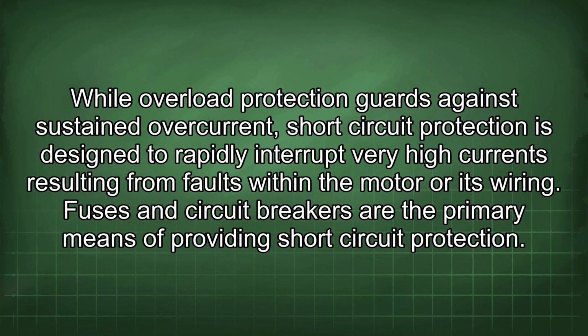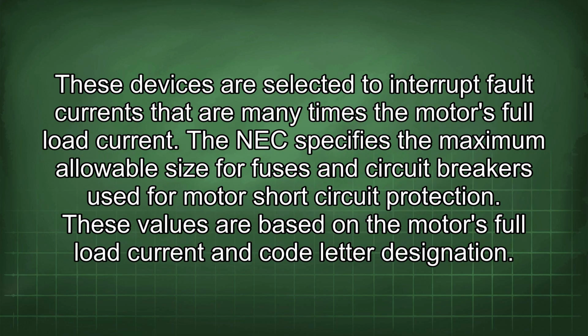While overload protection guards against sustained overcurrent, short circuit protection is designed to rapidly interrupt very high currents resulting from faults within the motor or its wiring. Fuses and circuit breakers are the primary means of providing short circuit protection. These devices are selected to interrupt fault currents that are many times the motor's full load current. The NEC specifies the maximum allowable size for fuses and circuit breakers used for motor short circuit protection. These values are based on the motor's full load current and code letter designation.